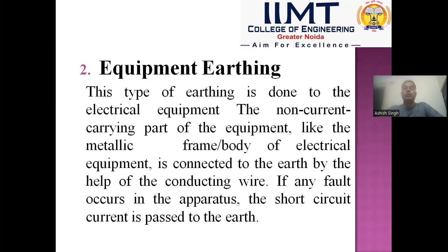And second one is equipment earthing. This type of earthing is mainly done for power apparatus or very large apparatus. In this type of earthing, the non-current carrying metallic part of the equipment or devices is connected to the earth electrode with the help of a short piece of wire. So if any leakage current comes on the surface of the body due to insulation failure, aging of insulation, or manufacturing defect, this earthing provides a safe path for dissipation of leakage current to the earth without harming apparatus and working personnel.